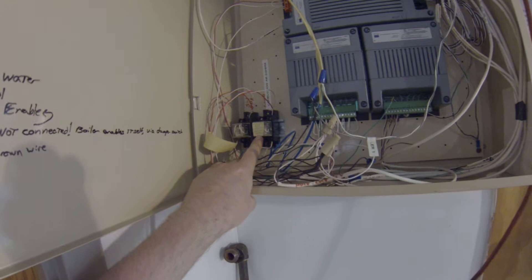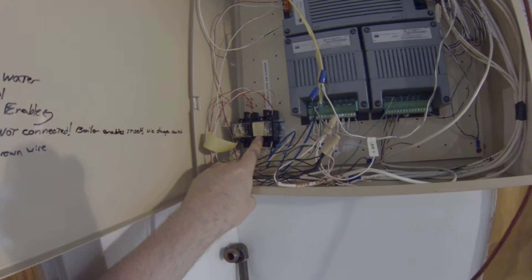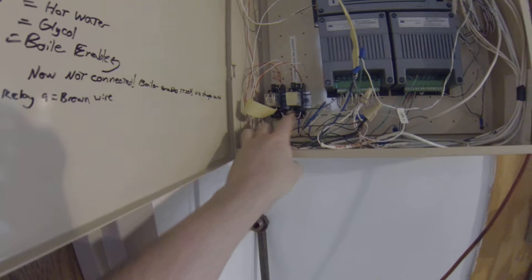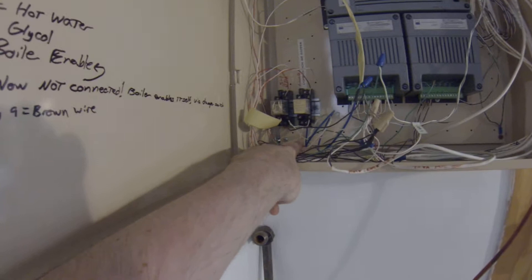The relays control things like the air handler and the combustion air damper. This relay controls the combustion air damper. It receives a signal from the boiler saying we want heat. That signal comes in here and switches this double throw relay. The white common wire is 24 volts AC and it's either going out the white or the blue wire here.